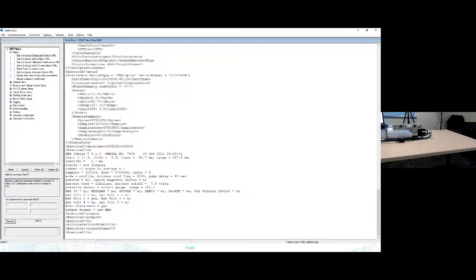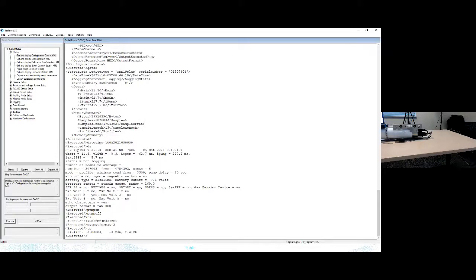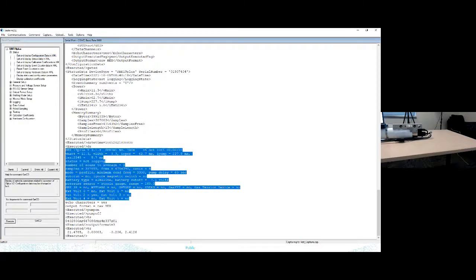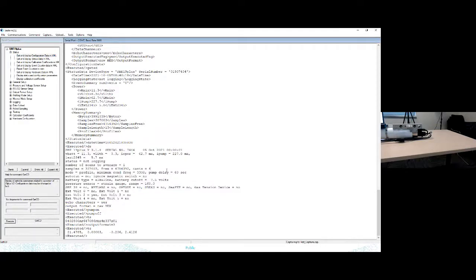The TS command. And that's going to tell us temperature, conductivity, and pressure of this room right here. So room temperature is about 21.47 degrees C. Conductivity is 0 because this is currently in air. You can change a lot of settings in CTerm, but the takeaway is this is how you communicate with your instruments, change settings with these commands, and create a log of the current status of your particular instruments.